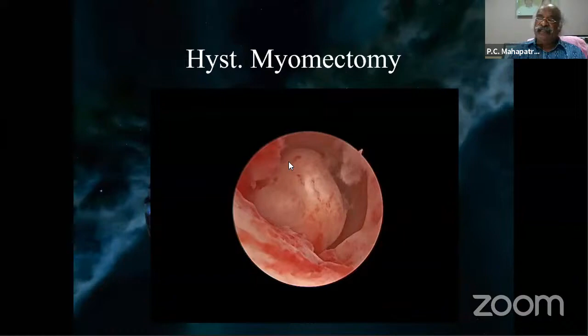The second option, if there is a small submucous myoma of about 1 centimeter or 2 centimeter, is a Versapoint bipolar electrode. The Versapoint is a separate instrument available from Johnson, but it is restricted to smaller submucous myoma. It can fulgurate it, but the tissue cannot be obtained. You cannot send it for biopsy. In larger sizes, you cannot do it, and that's very difficult. Therefore, hysteroscopic myomectomy by bipolar resectoscope is much better for that.